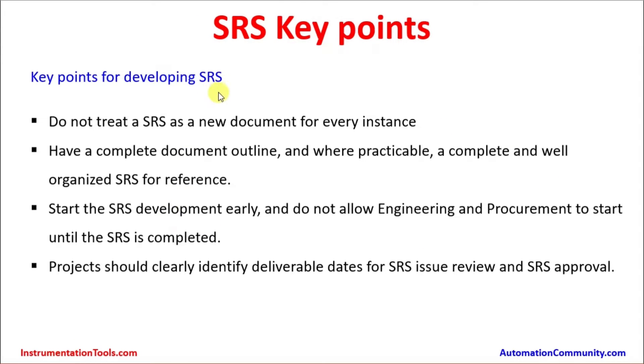Key points for developing the SRS: Do not treat the SRS as just any document — it is an evergreen document, and any SIS addition, modification, or deletion needs to be updated and captured in it. Have a complete, well-organized document outline for reference, and keep it clean for easy understanding. Start SRS development early and do not allow engineering and procurement to start until the SRS is completed, since it specifies the safety instrumented system prior to design. Projects should clearly identify deliverable dates for SRS issue, review, and approval.